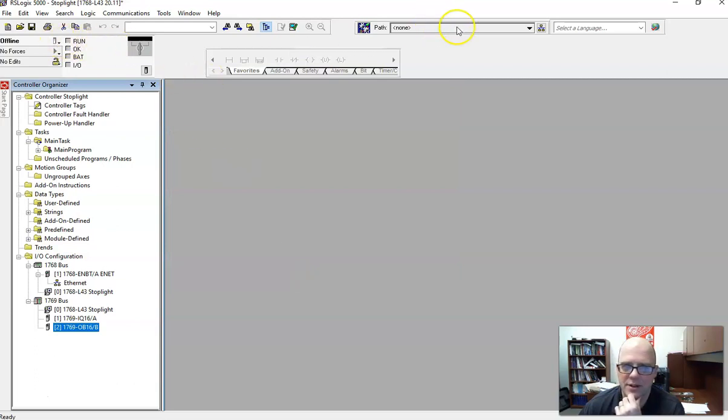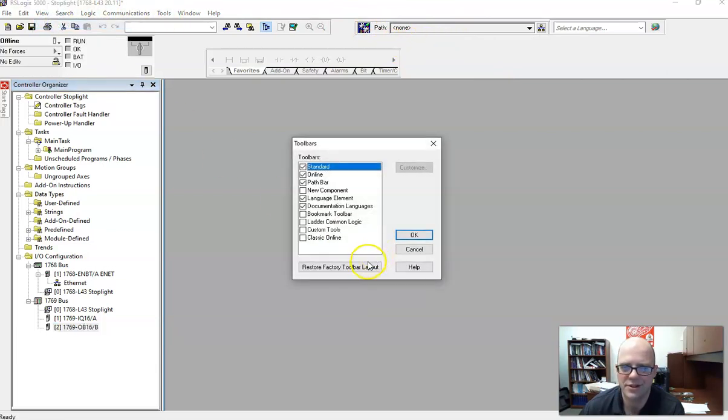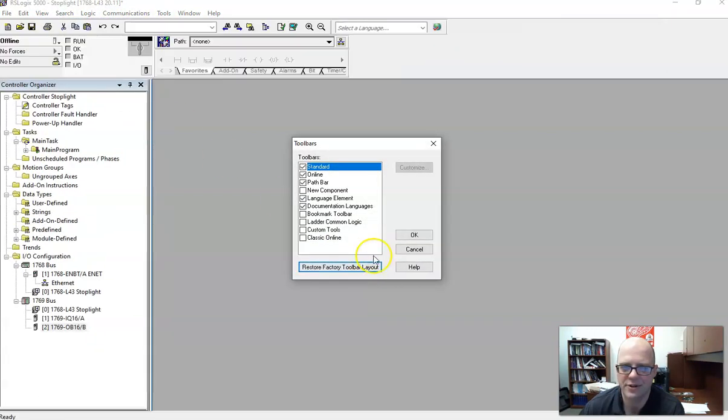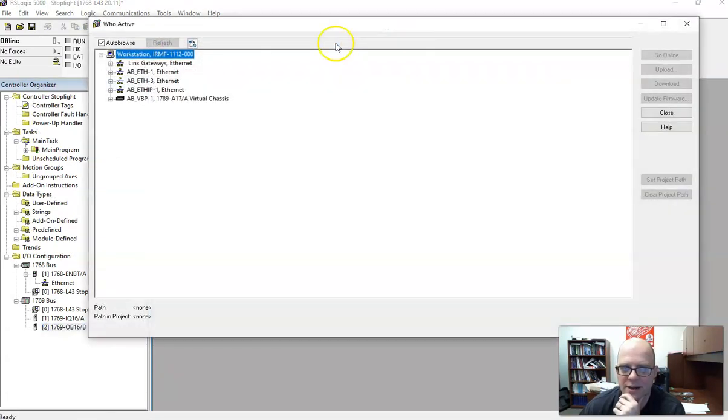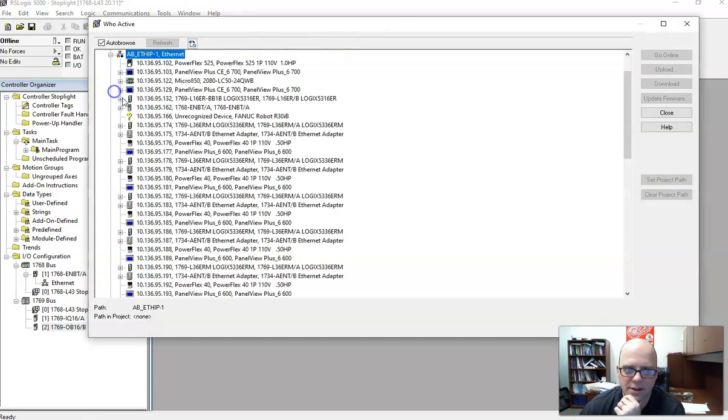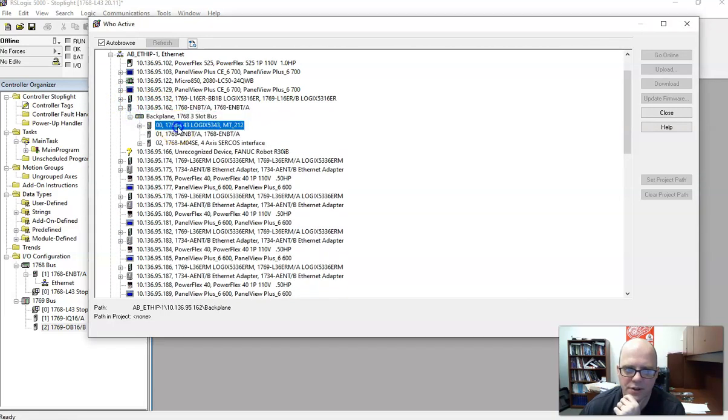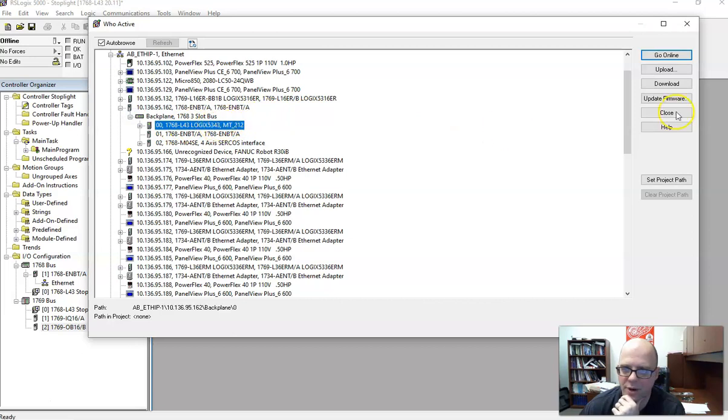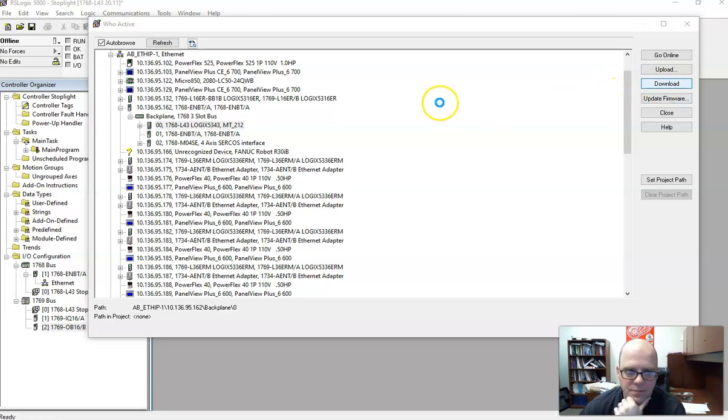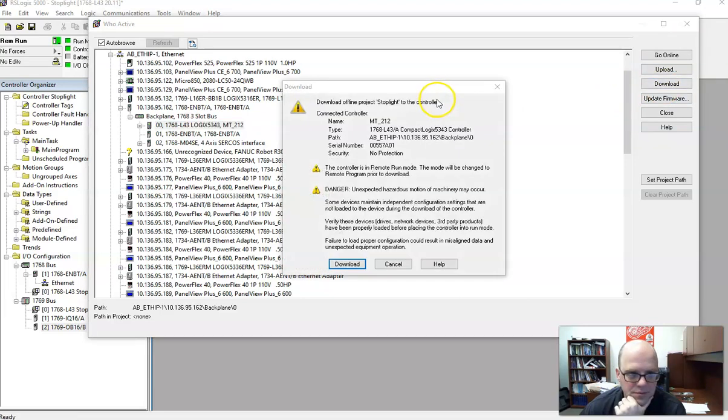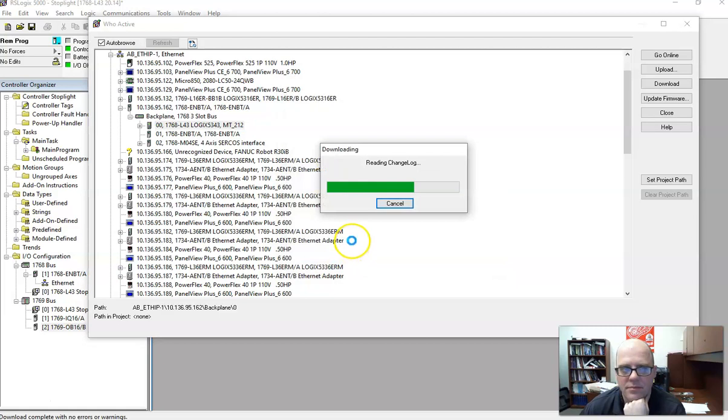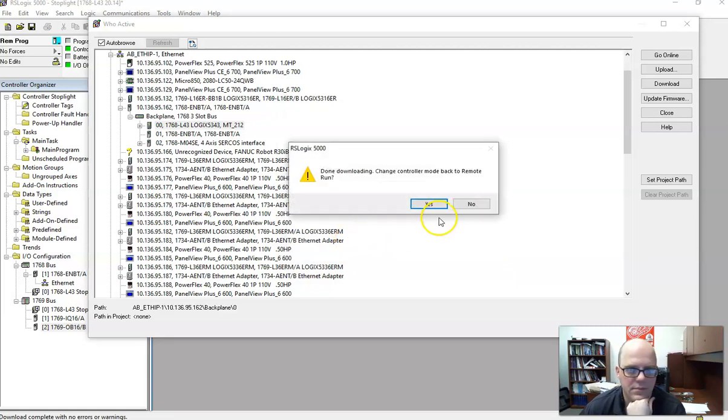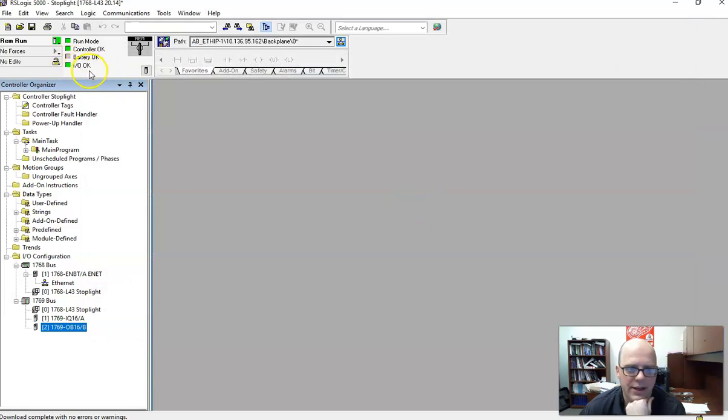And what we're going to do next is go up to the Communication Path. So this is all funky, you don't know what to do. Go up to View and Toolbars and just hit Reset Factory Layout. And then hit OK, and then everything goes back. So now let's hit the Communication Path to download. So IP, 162. Now, you're going to have to go through this in order to see your processor. And you know you've done it right when this shows up. Then you hit Download. Hit Download. Hit Yes. If you see IO OK, you're good.